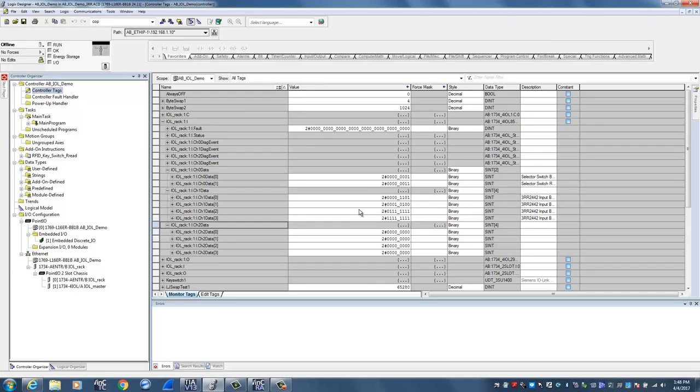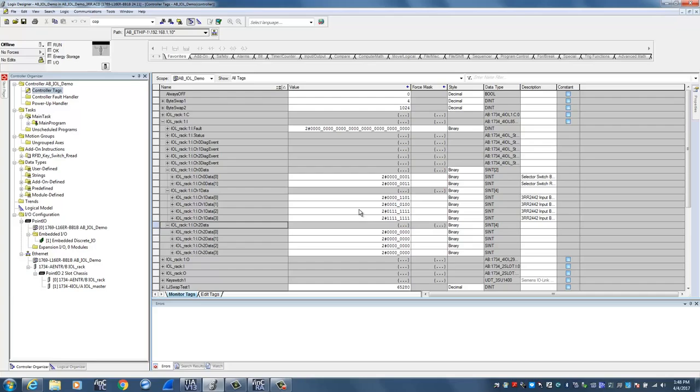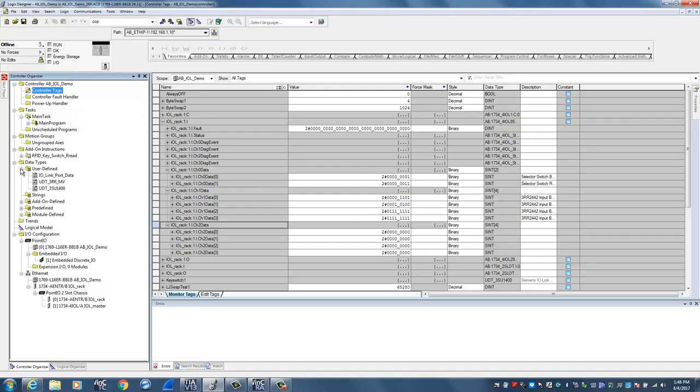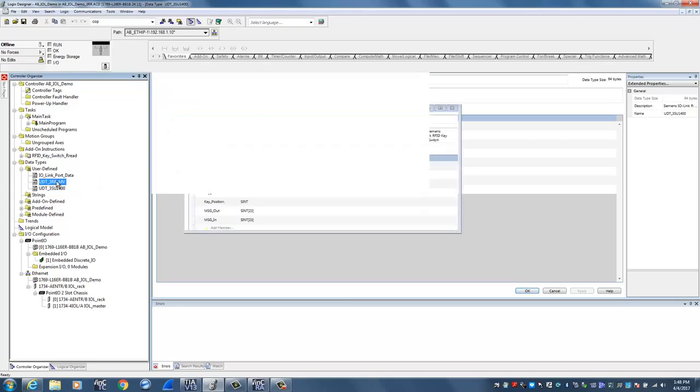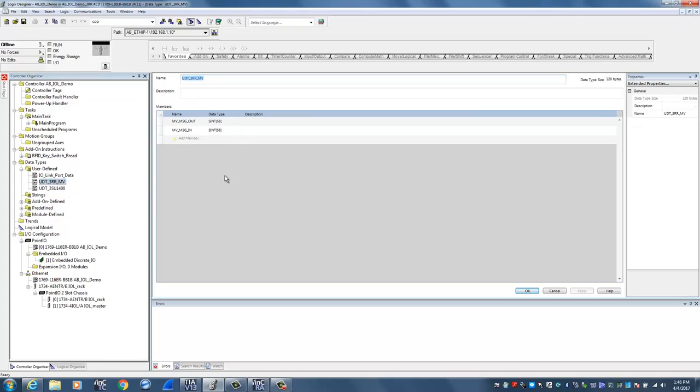In addition to cyclic data, several IO-Link devices also provide the ability to pull extra information acyclically. The way we do that in the Rockwell system is a combination of using UDTs or user-defined data types and the message instruction. So in our case here, if I come over here for user-defined data types, I've created two UDTs: one for the RFID key switch system, and if you look at that, it's several variables including a message_out and a message_in variable, length of 23 bytes each. And the second UDT is for the monitoring relays, and in this one I've created 58 bytes of input and 58 bytes of output information that will be communicated acyclically.